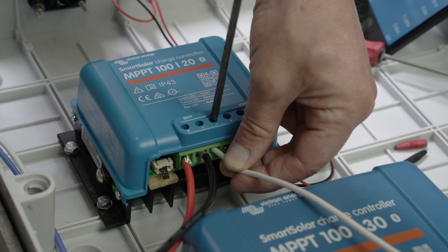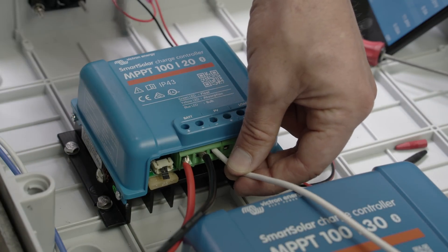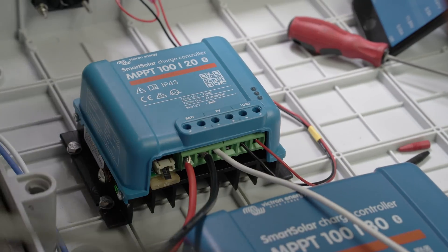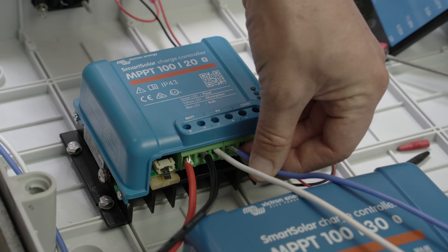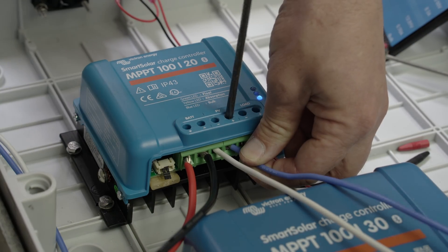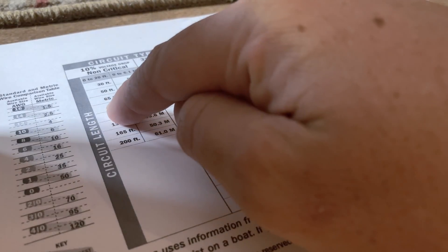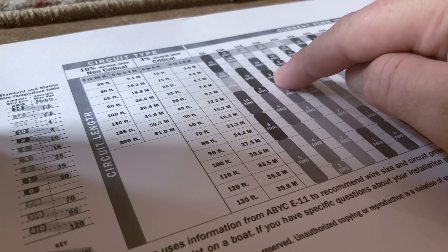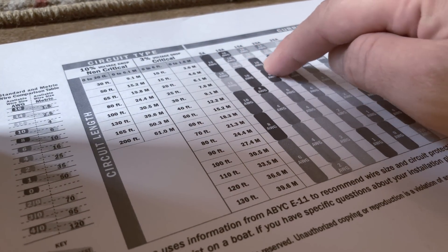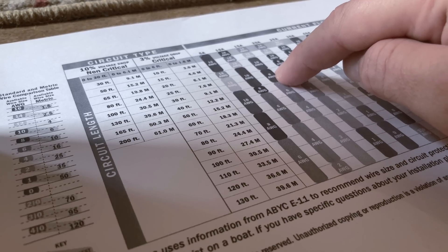Takeaway points for you. The cable's amp rating on the spec sheet is a safety limit only. If you exceed it, your problems may be much more serious than just voltage drop. For wire lengths under a meter, you're okay to use it as a sizing guide, but if performance matters for longer lengths, check the voltage drop charts first and plan your scintillatingly exciting wiring purchase correctly.